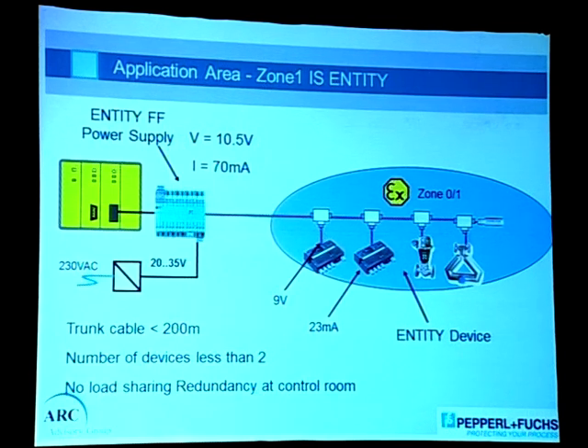So how we do that: this was the first method in the mid 1980s, when Fieldbus was introduced and we tried to adopt conventional intrinsic safety into Fieldbus, and this is how it looked. We have a power supply that limits the voltage and current according to conventional intrinsic safety. When we put in more devices, this current is not sufficient to connect anything more than 2 or at the max 3 devices. Or the voltage is not sufficient to drive more than 200 meters at the worst case. And if you consider all the safety factors, it becomes even worse. And the biggest problem is that intrinsic safety by principle does not allow redundancy. So we cannot put one more power supply in parallel. That is totally forbidden. If you put 2 power supplies in series, the IS parameters are totally not compatible.